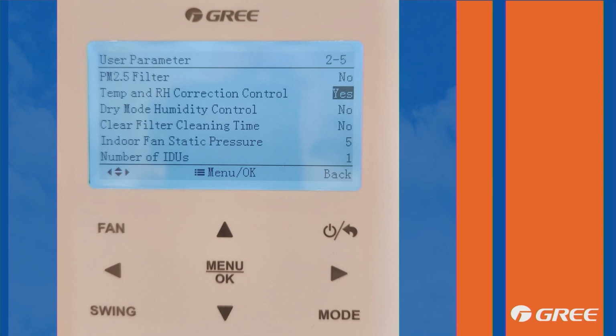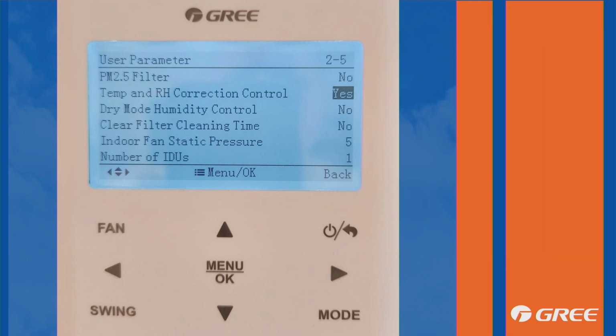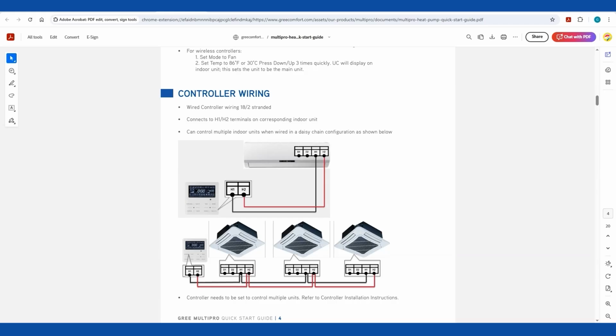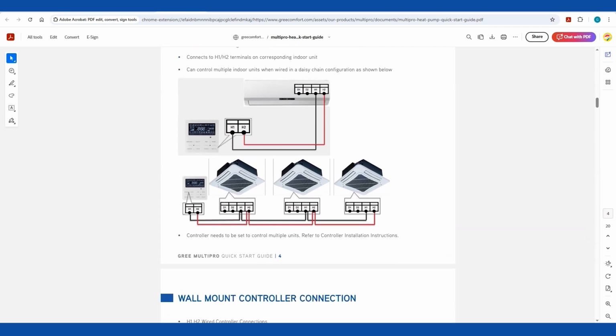So I've already done that, just showing you page 2, because I want to point this out right here. I would scroll with my arrows down to number of indoor units, and if we go by the wiring diagram I just showed you, we had 3 indoor units. You would change this to 3. This controller does not care how many indoor units are on the system. It only cares about how many indoor units you have attached to this controller. If that is set wrong, when you go to commission this unit, you're going to get an L9 error code, and it's going to keep you from commissioning the unit. So don't do that.